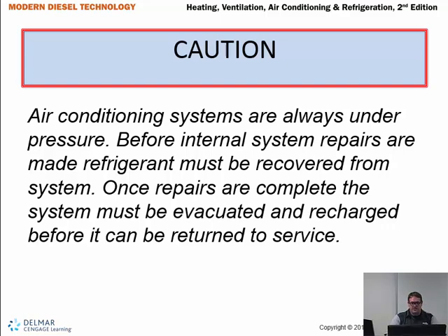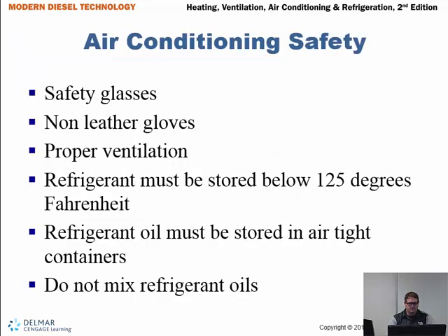Even if you yourself are the one that evacuated that system, we find oftentimes that the pressure can build back up again. That's why we do that 5-minute recovery period after we've sucked the system down into a vacuum. We wait 5 minutes to see if the system bleeds back up. And so that's what we're looking for there. So be very careful when you open these systems that there may still be some residual pressure in there.